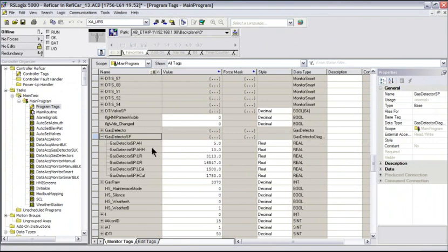For example, this is our warning, 5 ppm in this case. This is our gas alarm, 10 ppm. And these are the raw values for our under range, over range. And this is the window, the values for the definition of an in-cal status. This variable is not an array, it's just a UDT, so in this case it is used for all of the gas detectors in this program.